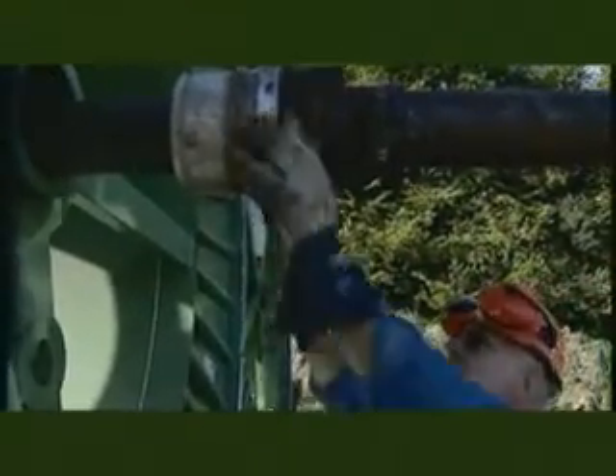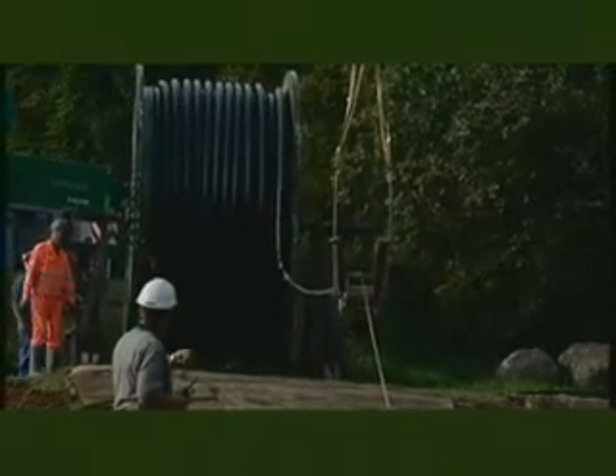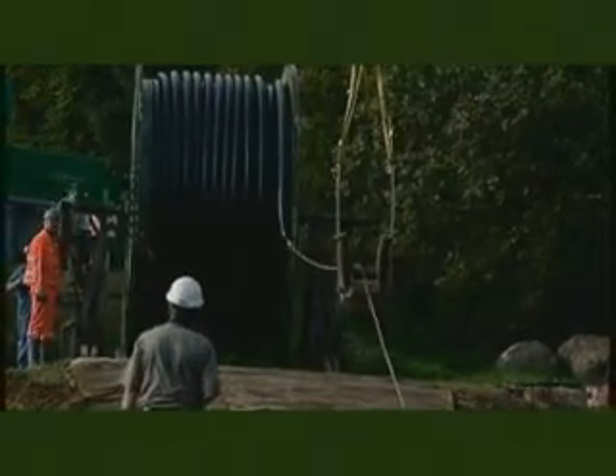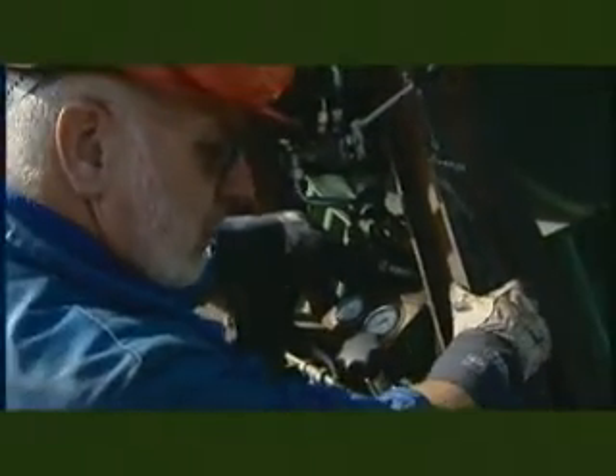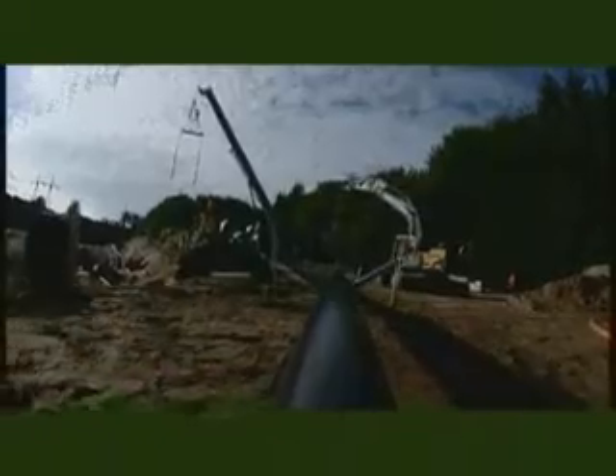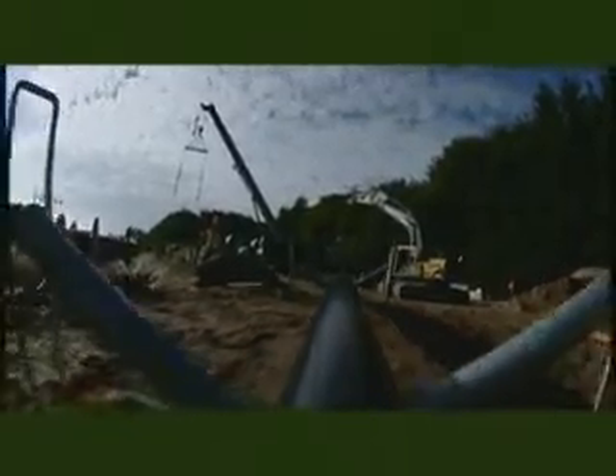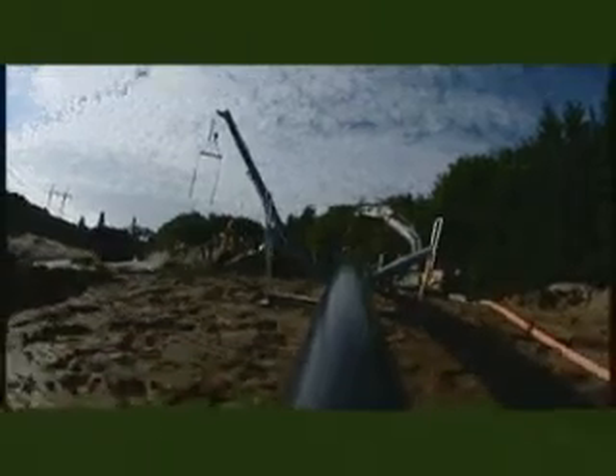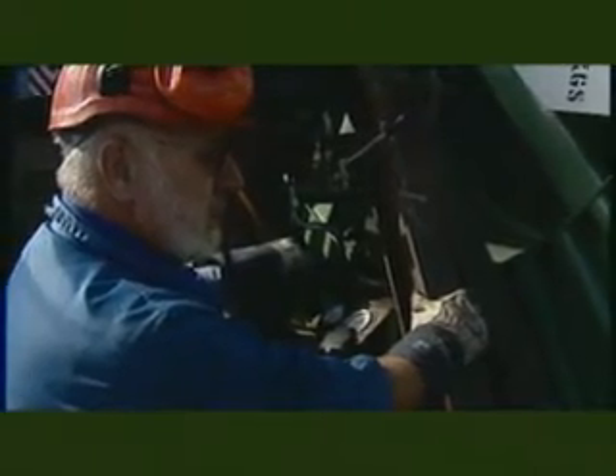When laying the submarine cables, a drum stand was used which was fitted with a mechanism that made it possible to turn the cable drum. The machinery was fitted with a hydraulic brake, so it was possible to brake the drum during laying. In undulating terrain, as here, where the first part of the section runs down a steep bank, the cable can run uncontrollably off the drum if it cannot be braked.